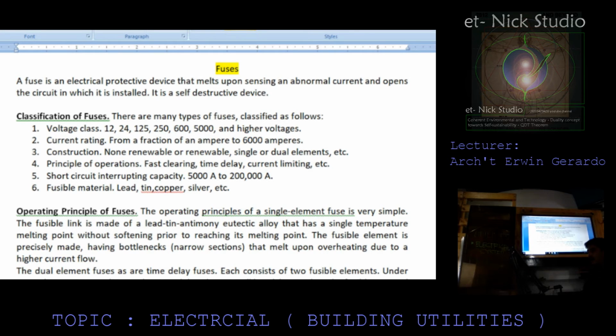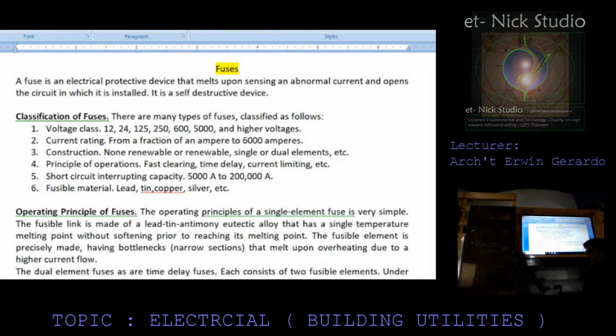Classification of fuses. There are many types of fuses, classified as follows. 1. Voltage class. It has 12, 24, 125, 250, 600, and 5000, and higher voltages. 2. Current rating, from a fraction of an ampere to 6000 amperes. 3. Construction: non-renewable or renewable, single or dual elements. 4. Principle of operation: fast clearing, time delay, current limiting. 5. Short circuit interrupting capacity, 5000 ampere to 200,000 ampere. Fusible material: lead, tin, copper, silver, etc.